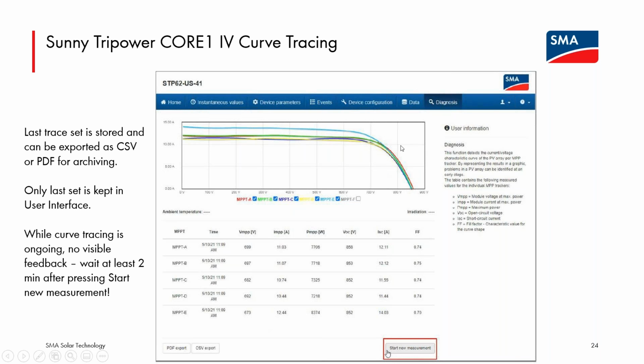Just remember that historical curves are not stored. So when you click Start New Measurement, anything that was logged is thrown away. So please offload the data once the curves are complete. And this is something you should see: if the strings coming into the CORE1 are all roughly the same, you should see very similar curves. This functionality is provided as an easy way for someone responsible for the maintenance of the system to check periodically the health of the array attached to the inverter.